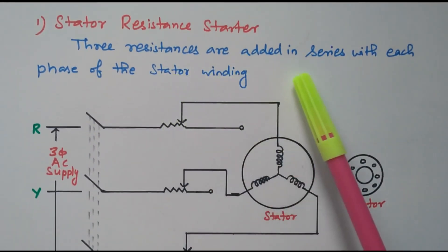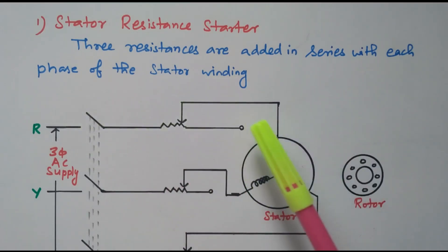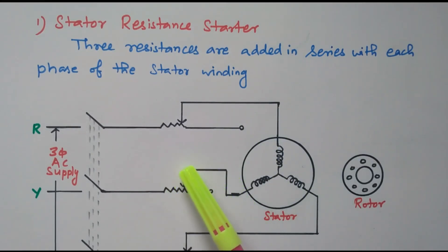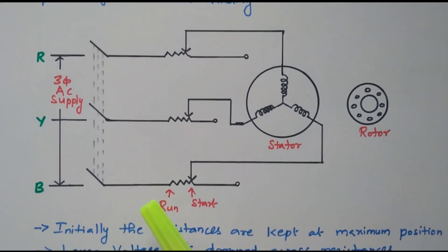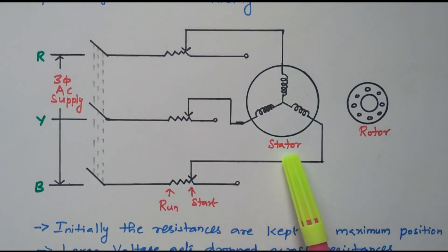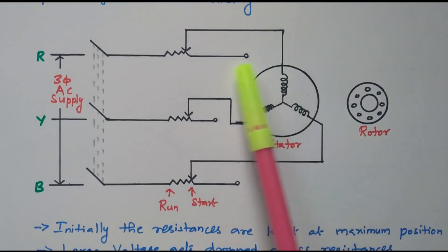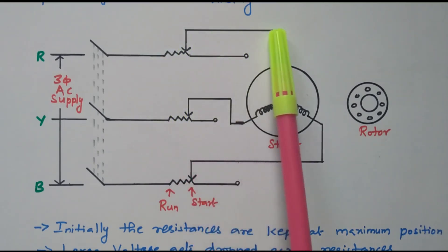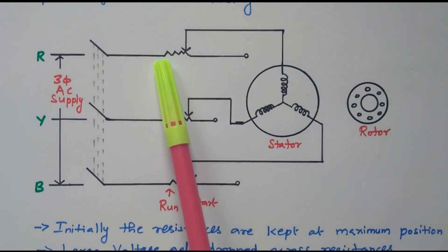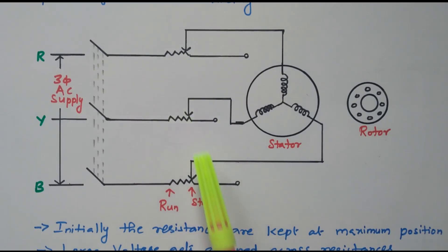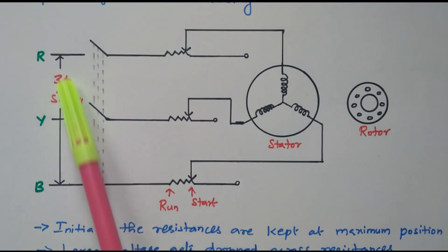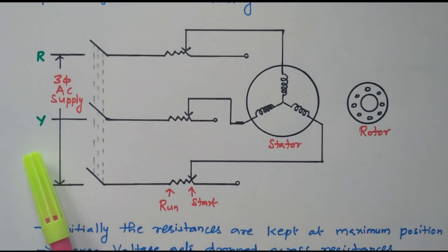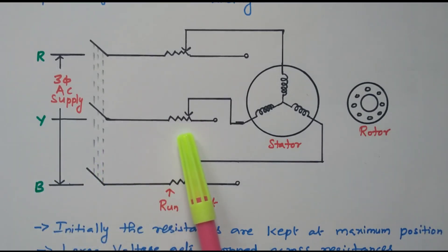In the stator resistance method, 3 resistors are added in series with each phase of the stator winding. Referring to the diagram: this is a 3-phase induction motor with a stator and a rotor, connected through 3 sets of resistance. This is the maximum resistance position — the voltage is fully dropped across the resistors and the remaining reduced voltage is applied to the stator. At the minimum resistance position, the full voltage is applied. Initially it is at the maximum resistance position, connected to the 3-phase AC supply through a switch in series with the 3 sets of resistance.